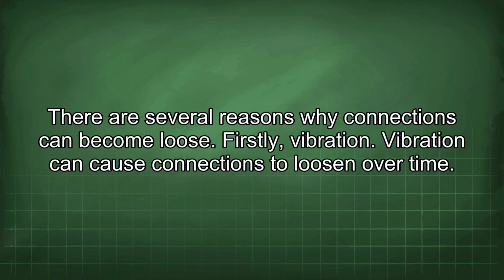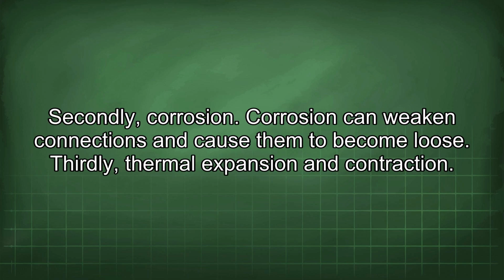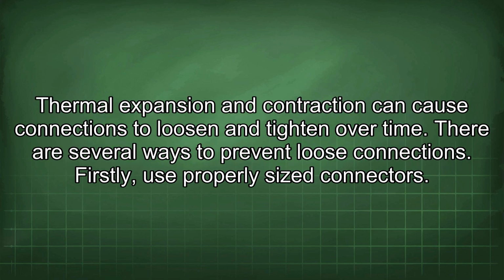There are several reasons why connections can become loose. Firstly, vibration. Vibration can cause connections to loosen over time. Secondly, corrosion. Corrosion can weaken connections and cause them to become loose. Thirdly, thermal expansion and contraction. Thermal expansion and contraction can cause connections to loosen and tighten over time.